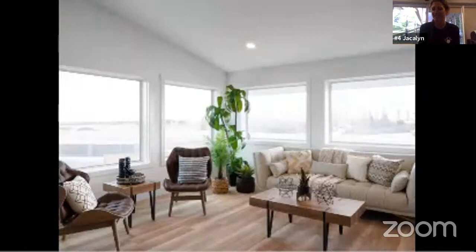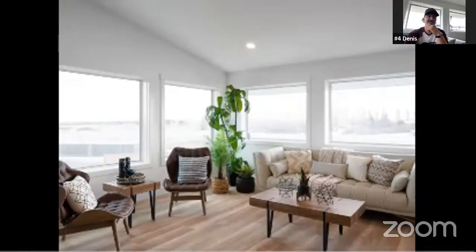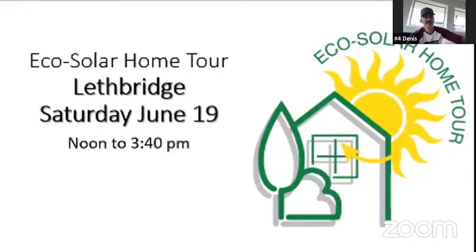Yeah. Anything else, Denis? No, other than the fact that the house is incredibly sealed tight, you do have to keep an eye on when you run your exhaust fans. So the kitchen exhaust above the range, you got to be kind of careful, because you will pull a negative pressure in the house, which you'll start to see frost and condensation build up on doorknobs and door locks and door hinges and stuff like that, if you're not running the HRV, making up that air as you're expelling it. Do you run your HRV as a function of the humidistat?